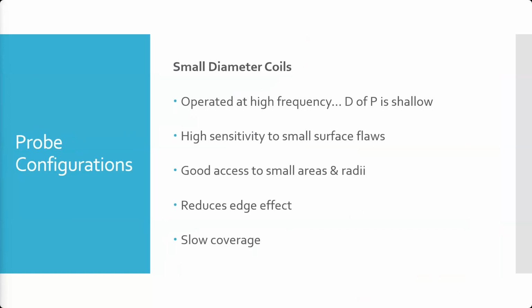One of the examples you'll have to show on every one of your tests is the edge effect with your given probe and tester setup. Because sometimes edge effect can look like a flaw. So you want to make sure: is it because your probe got too close to the edge, or is it because your probe found an actual flaw?